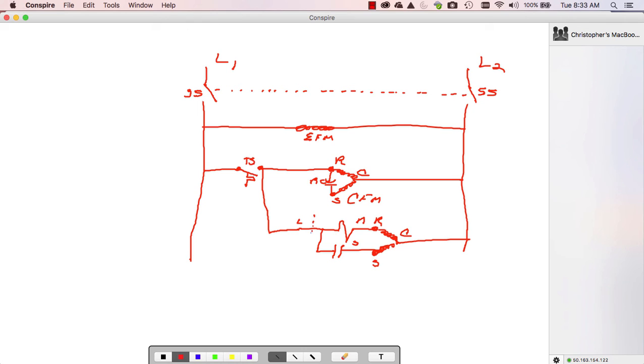Let's go ahead and throw a little box around this guy. So that is basically the identical circuit you have here. Let's label this compressor. And again, sorry about the wavy lines. The tablet I'm working on doesn't really let me see where my cursor is. So, again, evaporator fan runs constantly. Thermostat controls my condenser fan and my compressor.